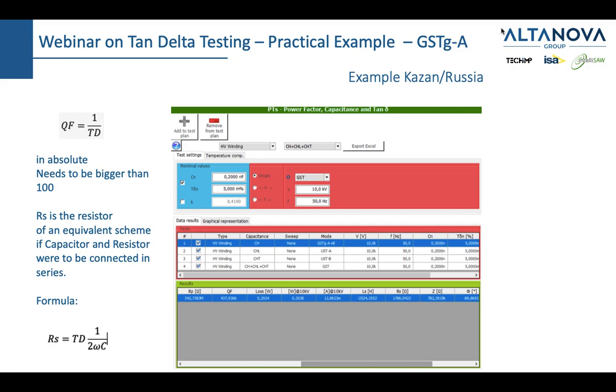There is a problem with that system because you cannot physically approach it, but you could maybe measure from some point further away from the tap, from the bushing, and then get an idea of what is the insulation of not just the bushing, but also the part where you are connected. What is the maximum capacitance measured using the ISA kit? As we said, it's about between 90 and 100 nanofarad.